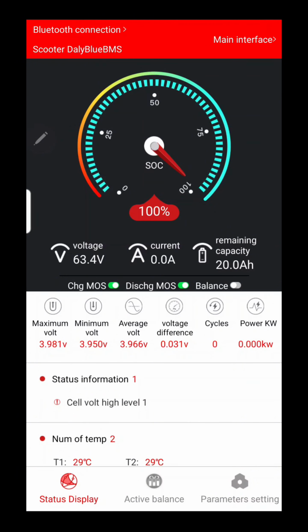They do various ones depending on how many strings of batteries you're using, what your S value is on your battery pack, so you can get the matching active battery balancer to match your BMS, plug it in and use it. It just means you've got two boxes and more wiring to do, because both the active battery balancer and the BMS need the sensor wires connected, so you need to run another set of sensor wires.